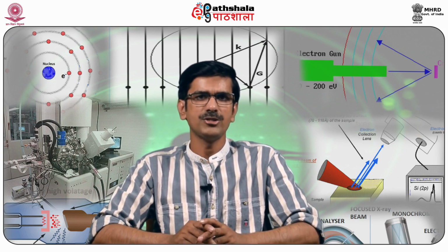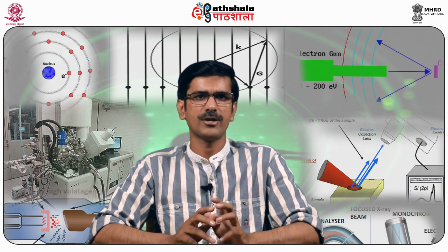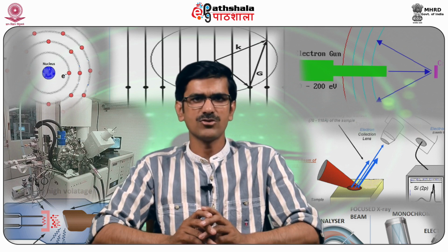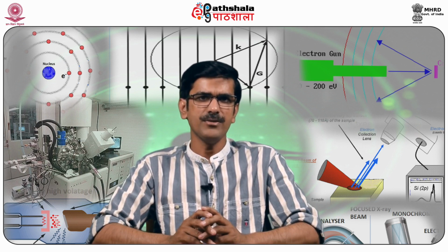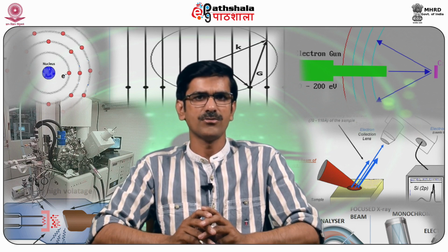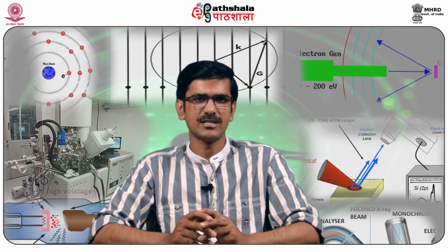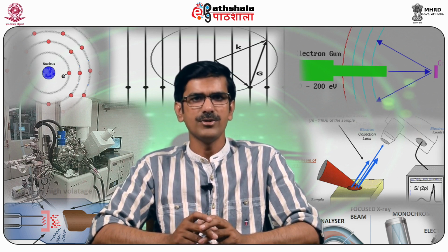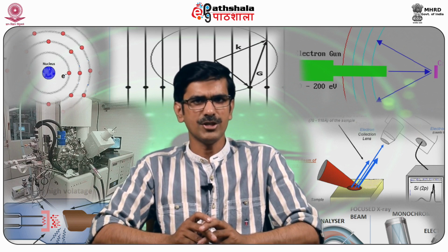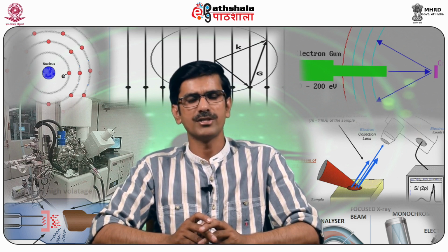A high vacuum environment is used to enable the emitted photoelectrons to be analyzed without interference from gas phase collisions. PES is rather picky when it comes to keeping the surface of the sample clean and keeping the rest of the environment free from interferences from things like gaseous molecules. The high vacuum that is used is always an ultra high vacuum, UHV, environment. An electron detector is used. The general description of PES is shown in this slide.